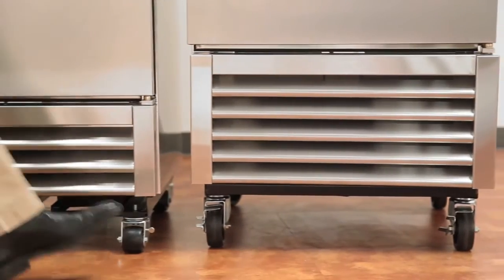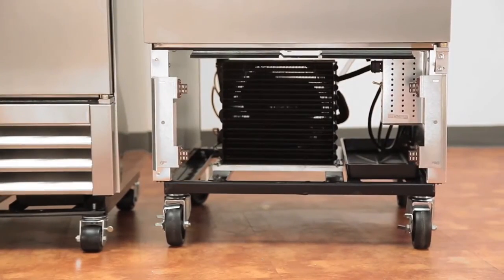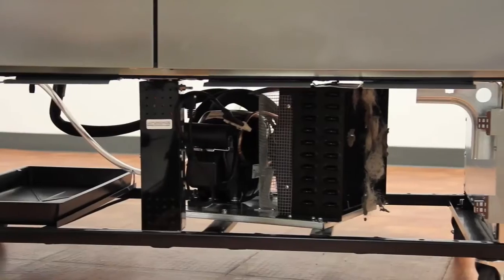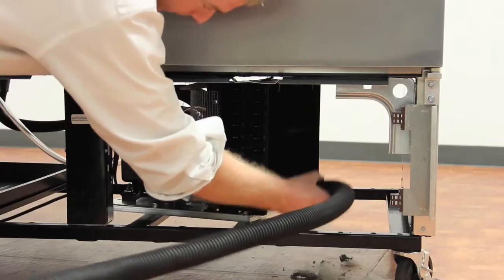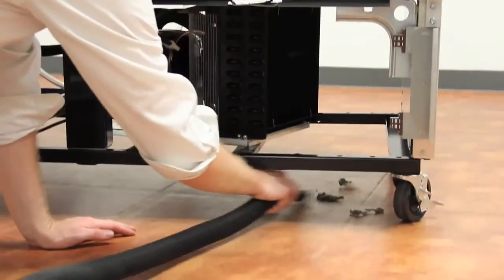A recommended rule is to check the condenser coil every month for the first three months of use. This will tell you how dirty your environment is. Generally, you should be cleaning your condenser coil every 60 to 90 days, depending on the environment in which it is used.